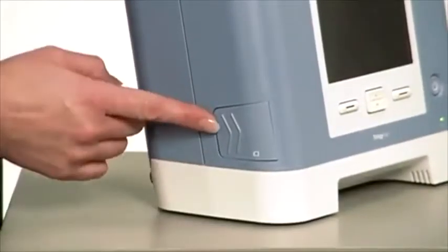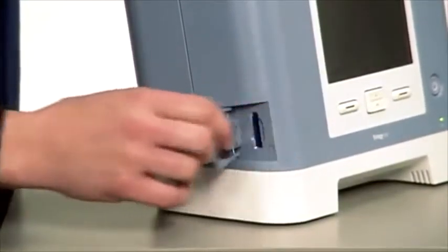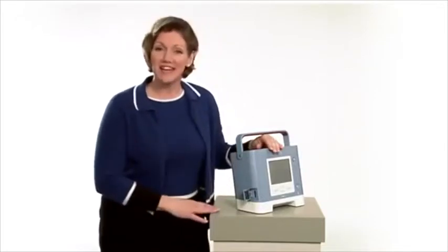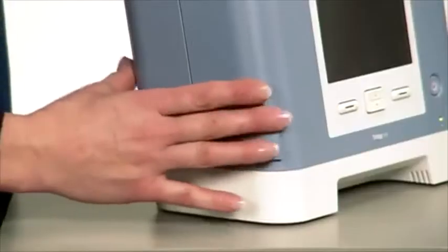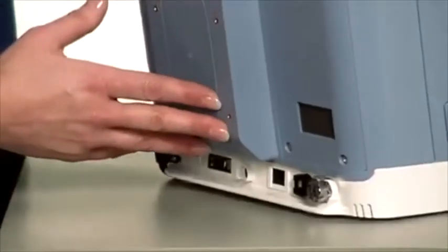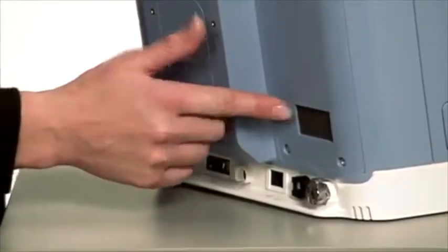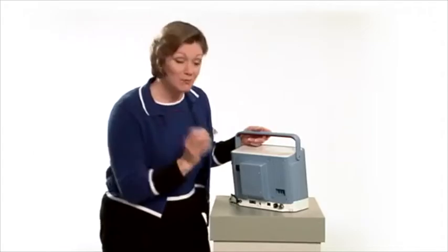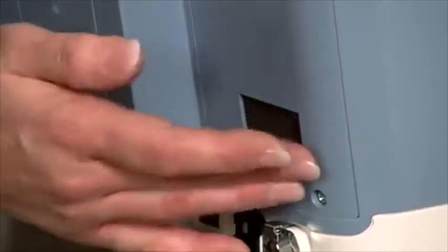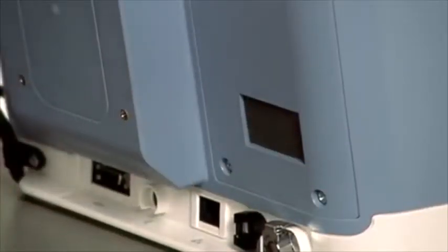The slot is for a secure digital or SD data card. This is an optional card that collects ventilation data for your physician. On the back of the Trilogy, you'll see an air inlet which holds a gray foam filter. The filter, which screens out normal household dust and pollen, is washable and reusable. You must have the filter in place when the device is operating.